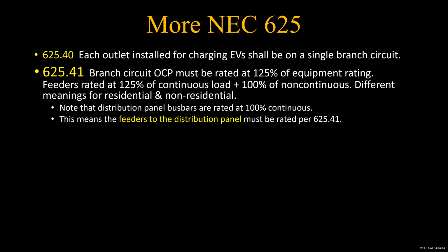And you may have a 150 amp distribution panel. Maybe you got a 200 amp main breaker, whatever. But you do your main load calculation, 100% at 10 kW at 100%. Well, we're going to do one in a minute, so we'll see what we need to do.